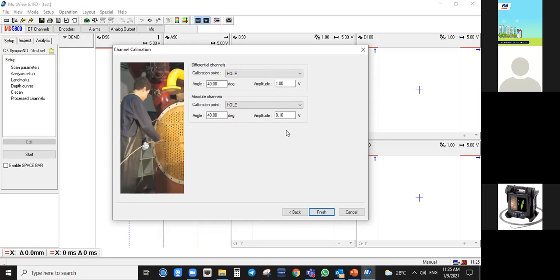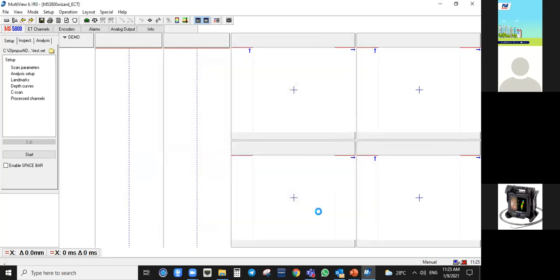On the absolute channel, the hole will still show you 40 degrees, and an amplitude of 0.1. Before, we used 1 volt here also, but the absolute channel is usually quite big, so it saturates. If it's saturated, then you will not get the whole picture of the defect. So usually they put it as 0.1 only because it's an absolute channel. Once all done here, you just press finish. Now just press finish, then it's configuring.